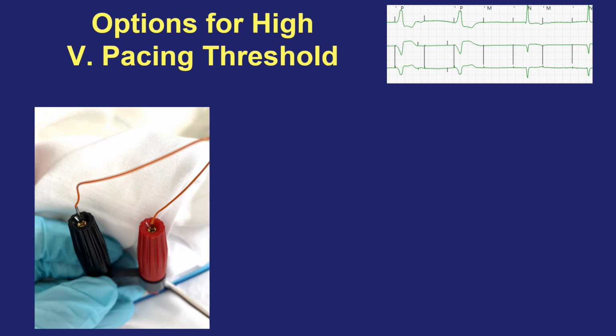There are methods that you can use to try to lower the pacing threshold by manipulating how these wires are hooked up. We talked earlier about the anode and the cathode. Here are our 2 orange ventricular epicardial temporary wires. One of them is hooked up into the cathode, the negative electrode, and the other is hooked up into the anode, hooked up to the pacer box. And often when there's inflammation, scarring around these wires at the level of the myocardium, it's not symmetric. It's not equivalent around the two. There may be one wire that's better than the other.